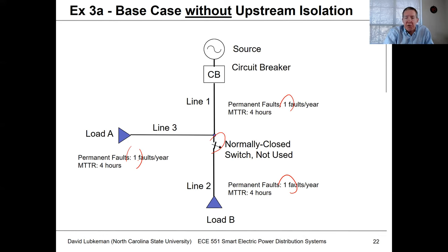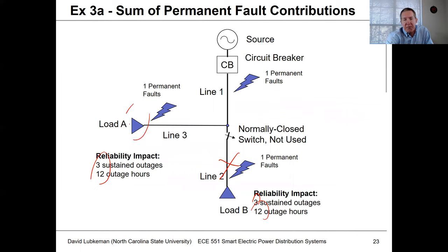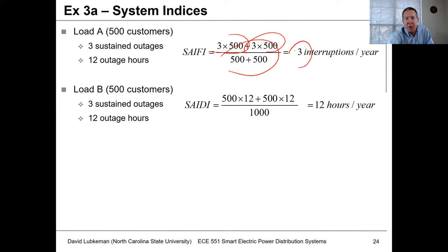Since the mean time to repair is four hours, there are four hours of outage associated with each of the three fault events. When we sum everything up, we get three outages and three times four gives us 12 outage hours for both customers. The fact that line section two has the fault means customers on line section three also suffer if we don't consider switching. Computing the indices: with the same number of customers at both load points, we get three interruptions per year for SAIFI and 12 hours per year for SAIDI — not a very good number.